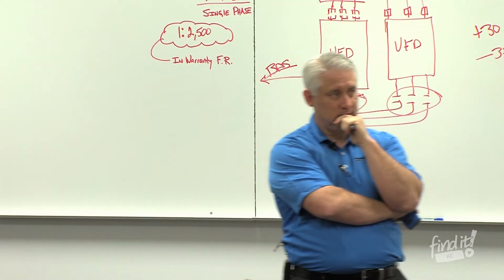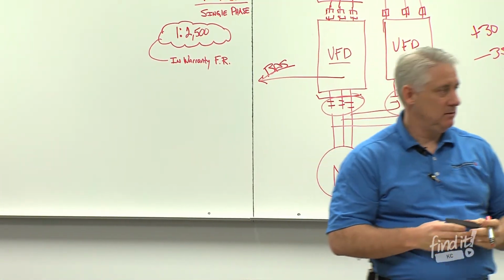You could also come in and manually do it by hand if you'd like and turn off that one motor, so that when that one's down, for whatever reason you want to maintain that cell or that pump or something, you don't have power going out to that guy. So it's something we do quite often. But you've got to have protection in there. Yeah, you've got to protect each motor.